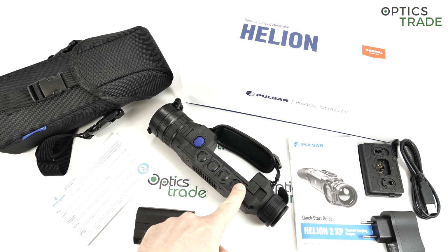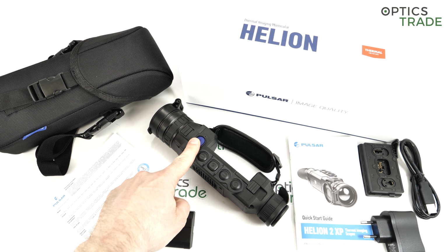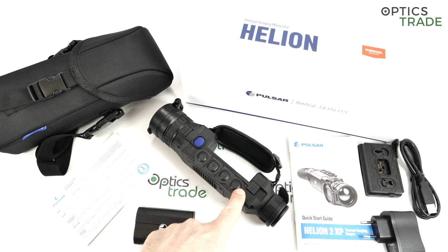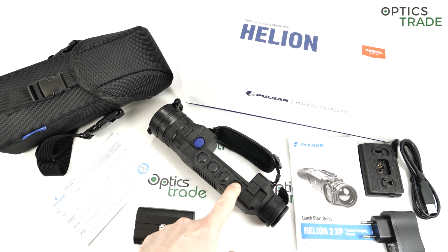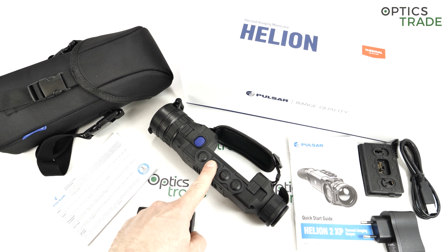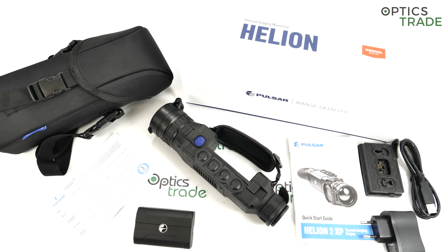The menus, you see, there are 5 buttons on top. 1 for the power, 1 for the recording of video, a direct record button. This is, I think, a much better solution than on the Axions, even though the Axions are so small that you are not able to put 1 additional button on them. But on Helions, I would say this is perfect. Then you have the menu button. Short press gives you the basic menu, where you can set the brightness and contrast. And the long press gives you the advanced menu, where you're able to change the identification mode, the Wi-Fi settings, and all other important settings which you are not setting every day.